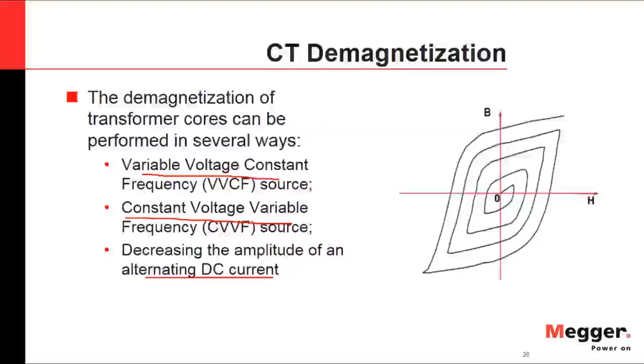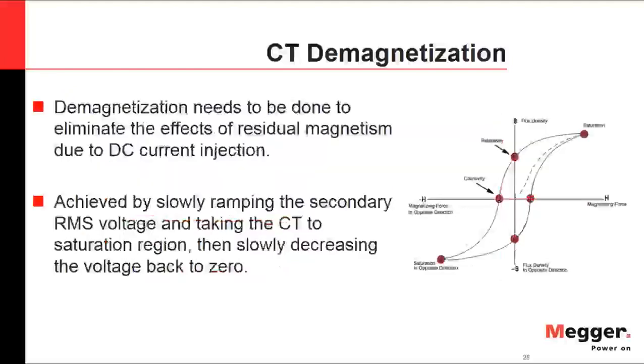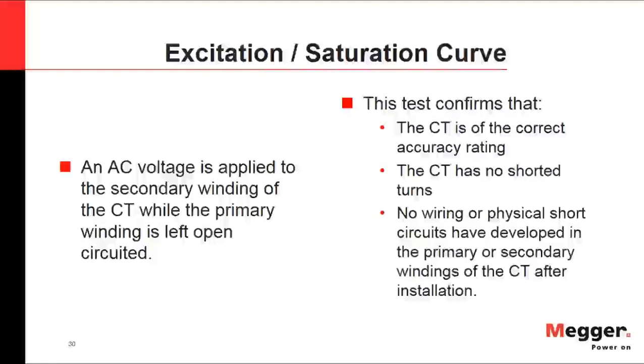To demagnetize a CT, you must first reach saturation, then apply a sinusoidal voltage and increase it until the core saturates, then decrease the magnitude back to zero — at which point you expect zero core flux and zero remnant flux. The excitation and saturation curve test following demagnetization is an AC test where we increase the AC voltage applied to the secondary winding and simultaneously measure the secondary winding current.